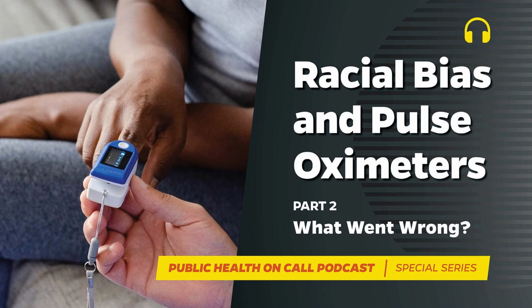And significantly, the recommendation includes having subjects across 3 cohorts of light, medium, and dark skin tone, as defined by the Monk Skin Tone Scale, a measure of skin color developed with Google. Unlike the previous scale, which originally only included white skin tones and later added 2 darker skin tones, the Monk scale spans 10 and was designed right from the beginning to be inclusive of the entire range of skin pigmentation in the US.